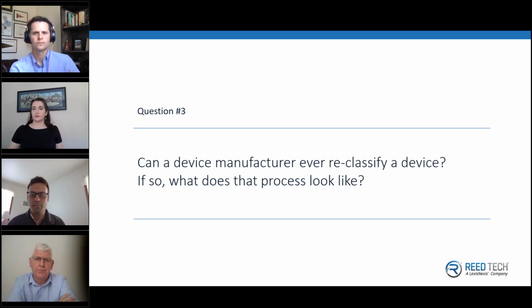Correct, and from a UDI perspective with registration, the intent is really to align with that. From a US GUDID perspective, beyond the device being published in the registry, you can make changes. You could add, delete, and edit the attribute for GMDN. That's a good thing, meaning it wouldn't trigger a new device identifier to be assigned, basically a new record to be submitted. You maintain the existing record.